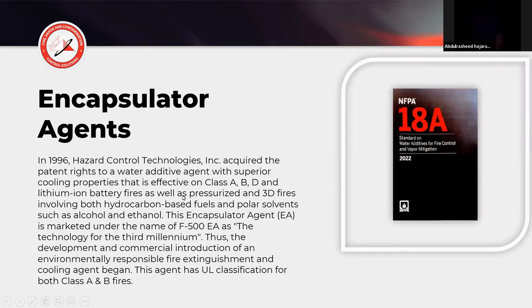When we start looking at the encapsulator agents, there's an NFPA standard that this agent falls under, and it's NFPA 18A, and it was just done here in 2022 with the most recent edition. And when you start going through this standard, you'll see how it's able to work on all the different classes of fires. The A's, the B's, the D's, lithium ion batteries, and we'll get into that as we continue on.